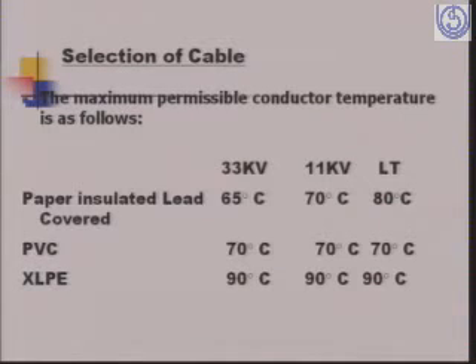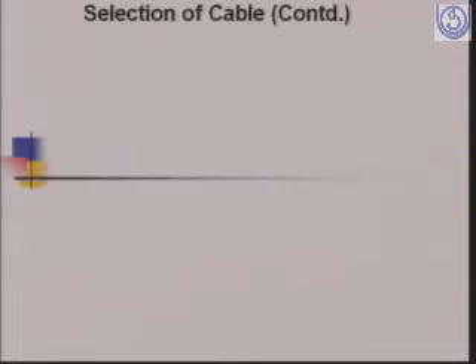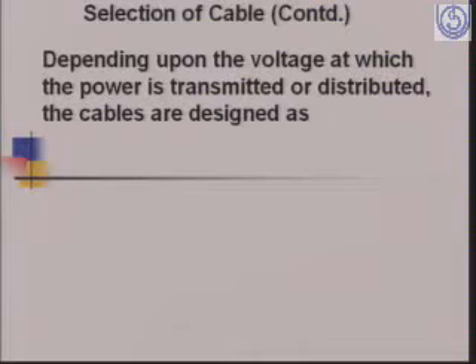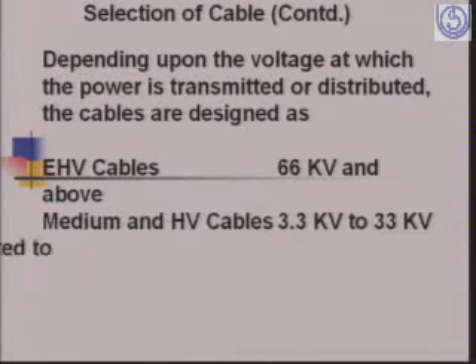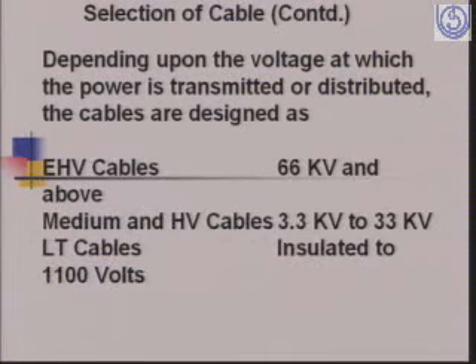Well, we were talking about the maximum permissible conductor temperature for various voltages and for various types of cables. This slide indicates what are the permissible conductor temperatures for various cables, depending upon the voltage at which the power is transmitted.